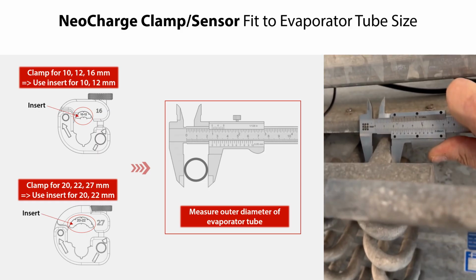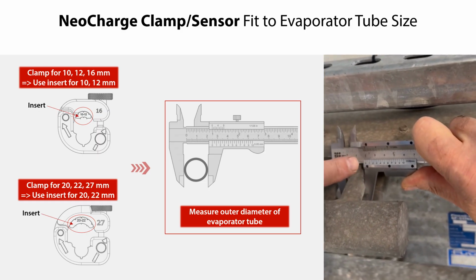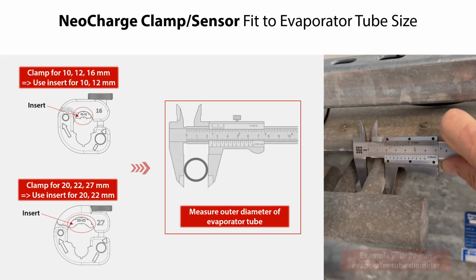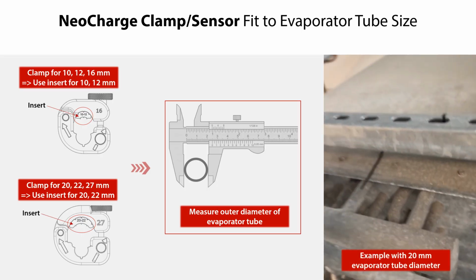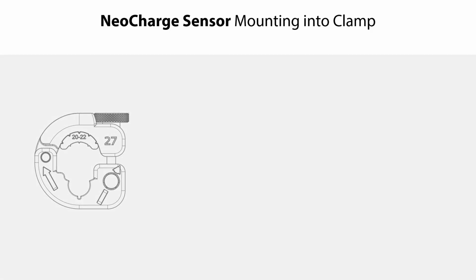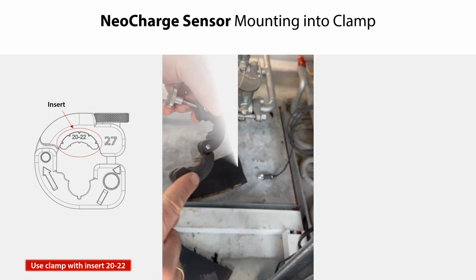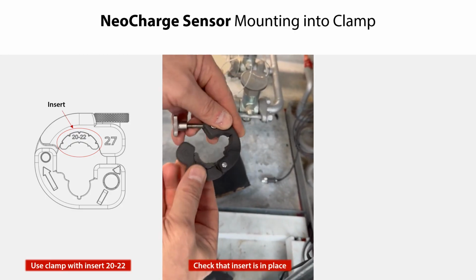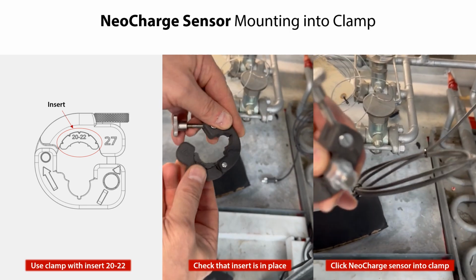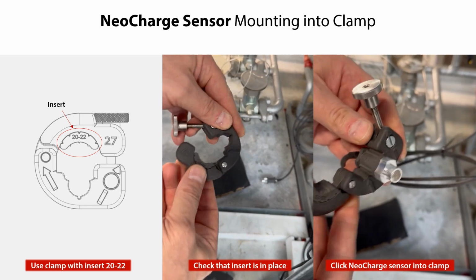This is to ensure that the clamp with sensor will fit correctly onto the evaporator tube. In this example, we measure the diameter to be 20 millimeters. Since we have measured the evaporator tube outer diameter to be 20 millimeters, we need to use the clamp with the insert included. Therefore, ensure that the insert is in place as shown here. Then click the Neocharge sensor into the clamp as shown here.